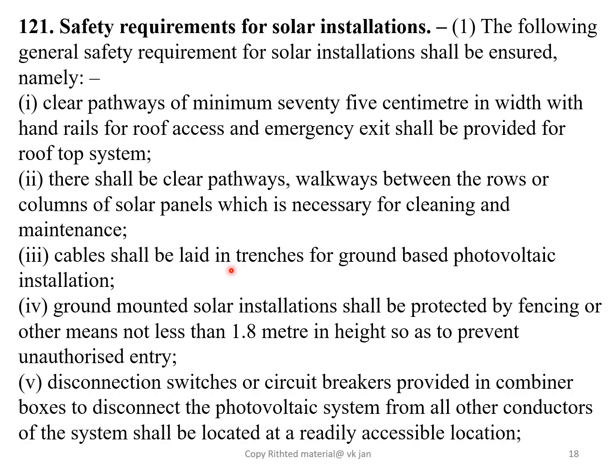Fourth, ground-mounted solar installations shall be protected by fencing or other means not less than 1.8 meter in height so as to prevent unauthorized entry. Fifth, disconnection switches or circuit breakers provided in the combiner boxes to disconnect the photovoltaic system from all other conductors of systems shall be located at a readily accessible location. Friends, let me make it clear that these are only some of the rules.